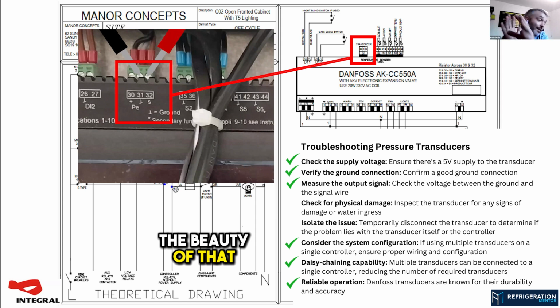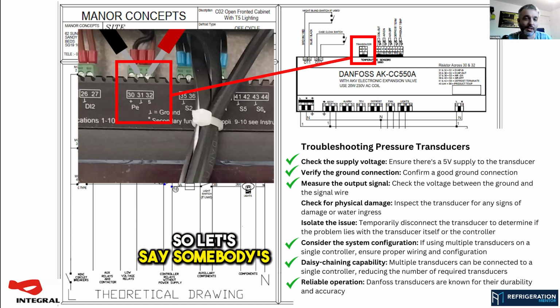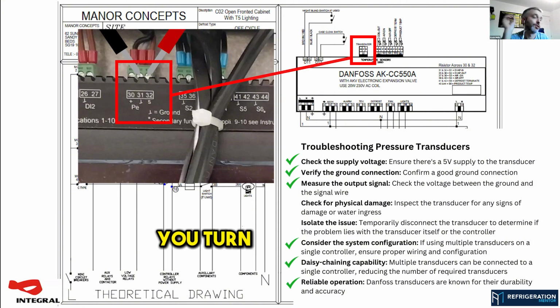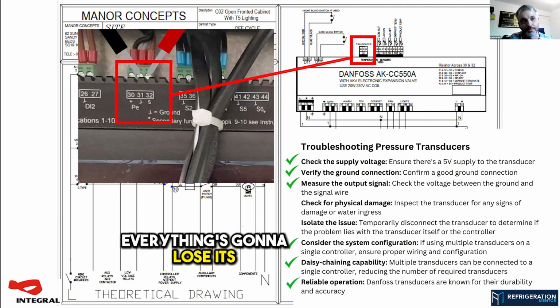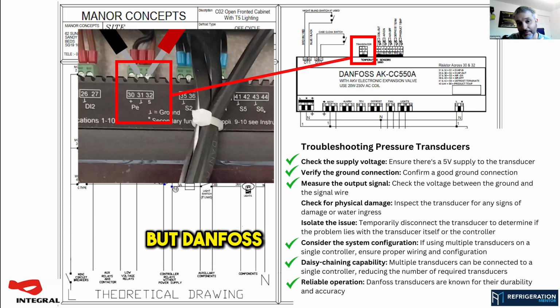The beauty of that is if you turn any case off, the transducer still gets power, you still get your reading. When we come to Carel in a little bit, you can't do that. You can only power the transducer from one controller. So if, let's say, somebody's doing a case clean, if you turn the controller off that's powering the transducer, everything's going to lose its evaporating temperature. But Danfoss is really good with that. You can feed, I think it's up to 10 cases off one transducer.